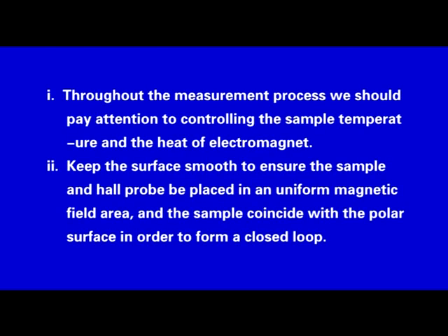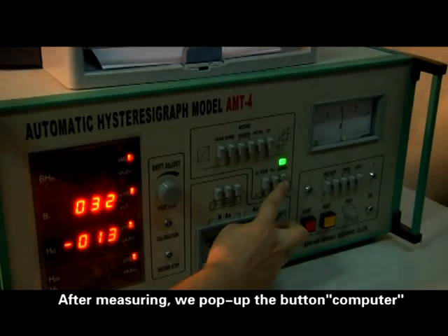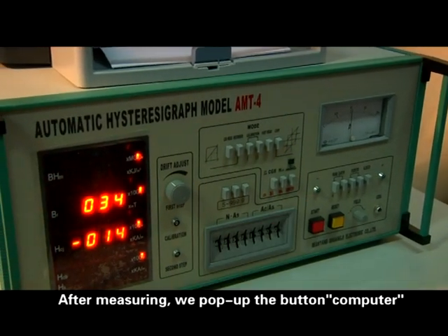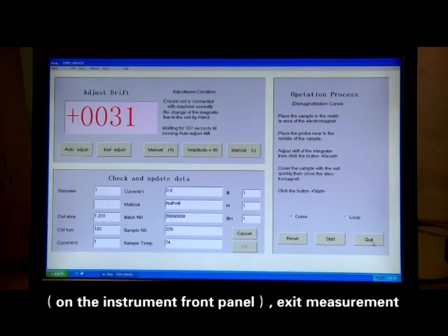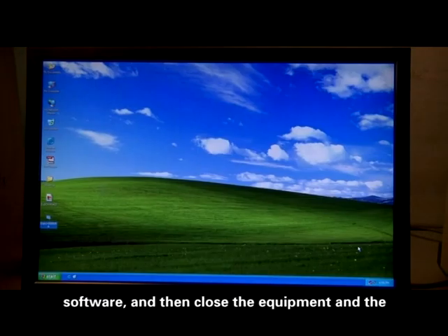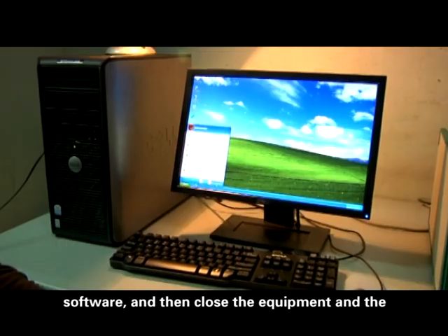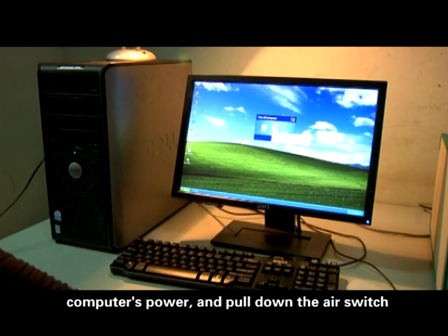4. Notice. 1. Throughout the measurement process, we should pay attention to controlling the sample temperature and the heat of electromagnet. 2. Keep the surface smooth to ensure the sample and Hall probe be placed in a uniform magnetic field area, and the sample coincide with the polar surface in order to form a closed loop. 3. After measuring, we pop up the button computer and the instrument front panel, exit measurement software, and then close the equipment and the computer's power, and pull down the air switch.